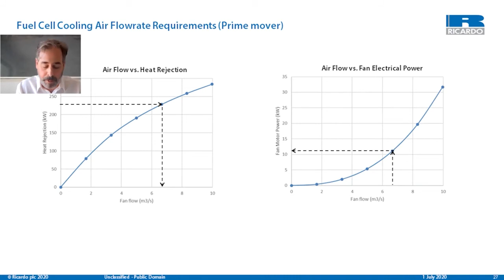On top of that, we have to layer in other devices we're trying to reject heat from - air compressor, other components, power electronics, as shown on the previous slide. But you also have to take into account the electrical power budget required to drive the pumps and fans. Depending on how aggressive the cooling needs to be, you can have an additional 30 to 50 kilowatts of electrical power that needs to be planned for, along with what conveyance mechanisms for that electrical power will be used.